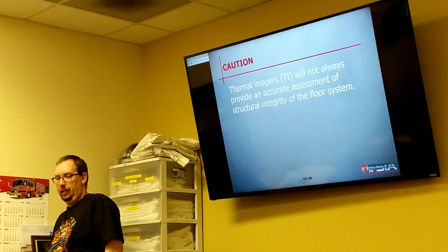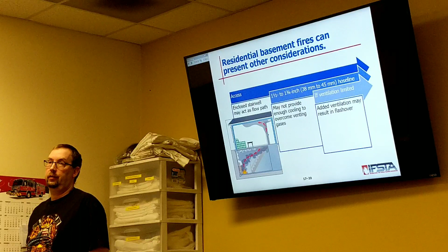Other considerations: enclosed stairwells are going to act as a flow path, like a chimney you're climbing up or down. 1.5 inches or even 1 3/4 may not be enough. You may have to pull a 2.5 to the stairwell and crack it open. You need enough to overcome the cooling and the venting of the gases.